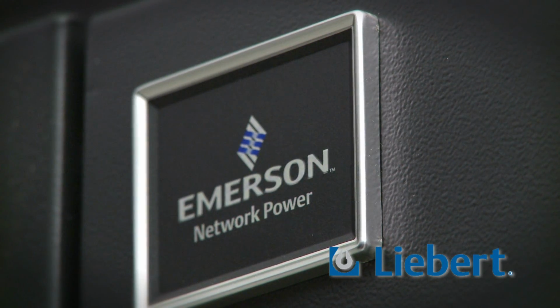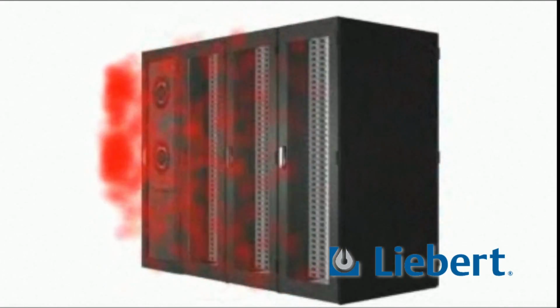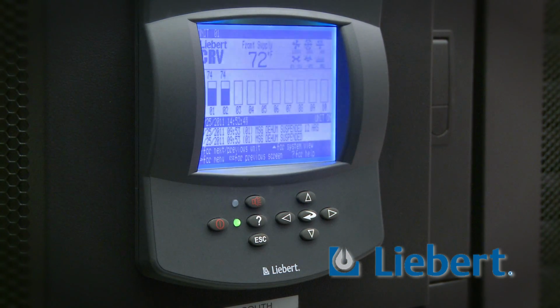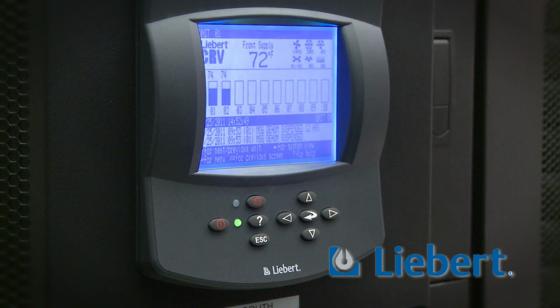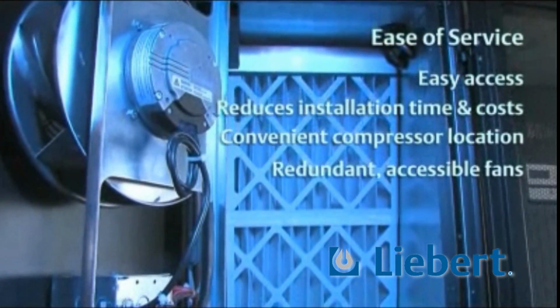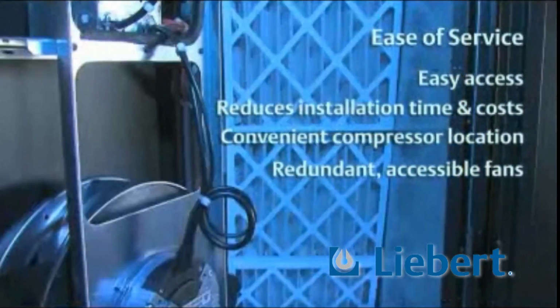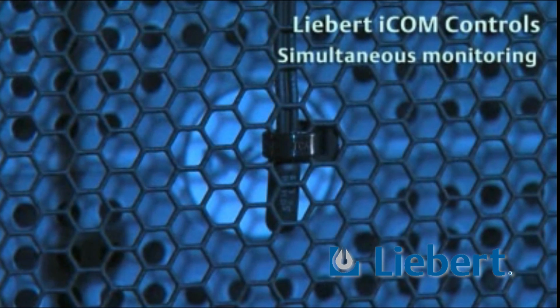With rack, power, and cooling, the majority of our research was based on cooling. And based on this research, the rack-sized Liebert CRV provided high-capacity cooling in a small footprint and features control systems that modulate unit performance in real time based on conditions in the row, monitoring up to 10 racks with 20 sensors precisely controlling air temperature, humidity, and filtration.